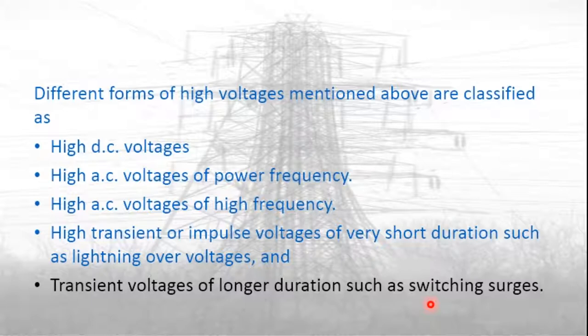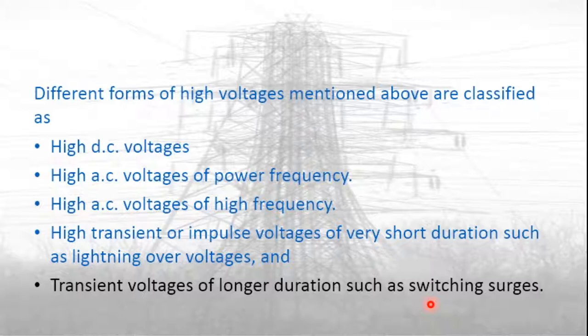Normally in high voltage testing, the current under conditions of failure is limited to a very small value. But in certain cases like testing of surge diverters or short circuit testing of switchgear, high current testing with several hundred amperes is also very important. Testing of surge diverters requires high current of the order of several kiloamperes. Therefore, the test facility requires both high voltage and high current, and high impulse current generation is also required along with high voltage for testing purposes.